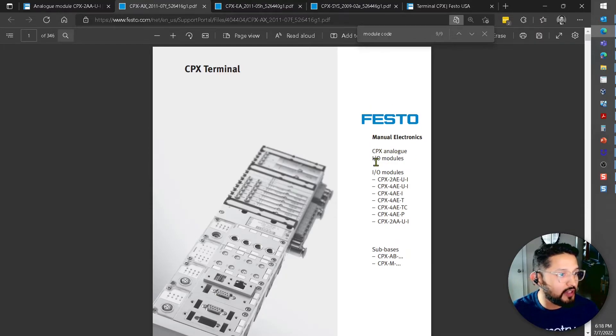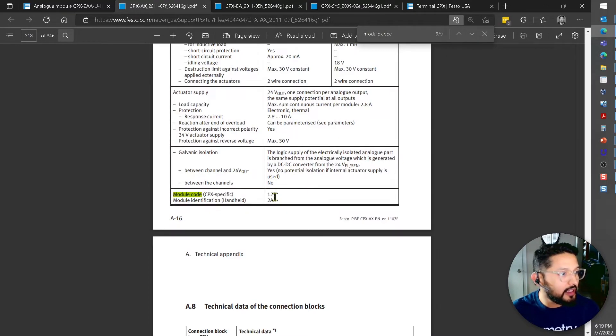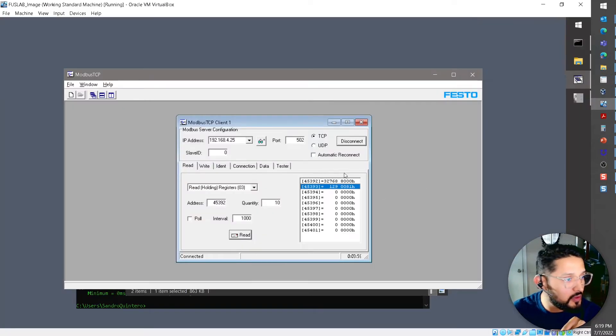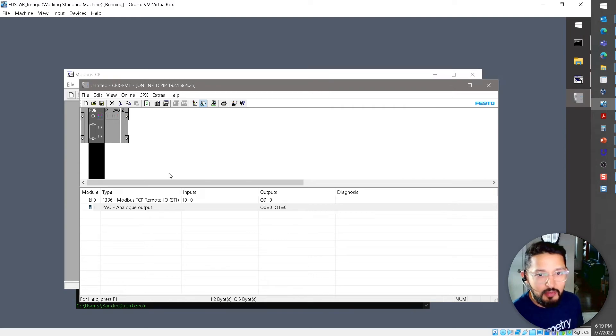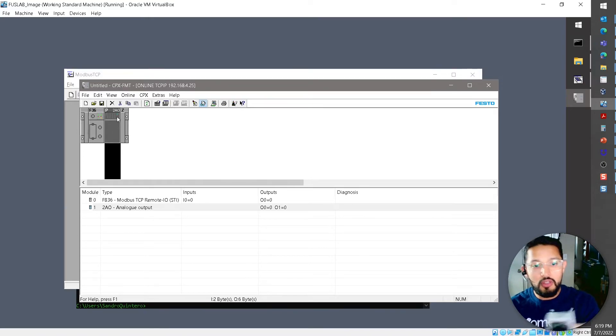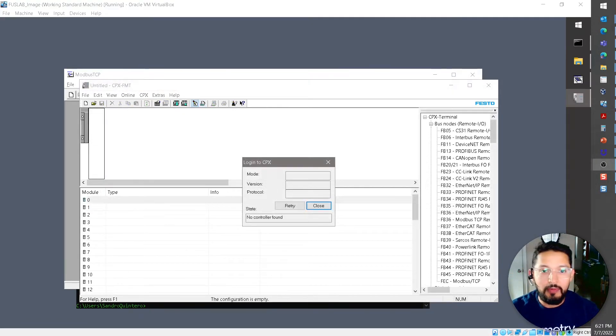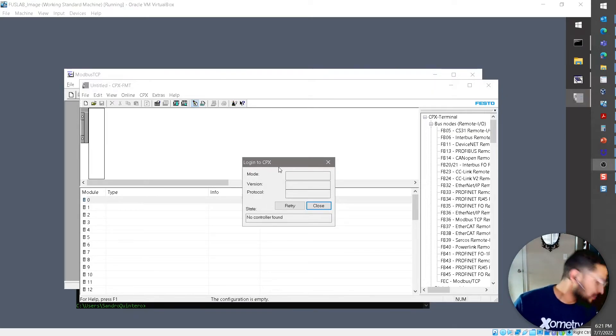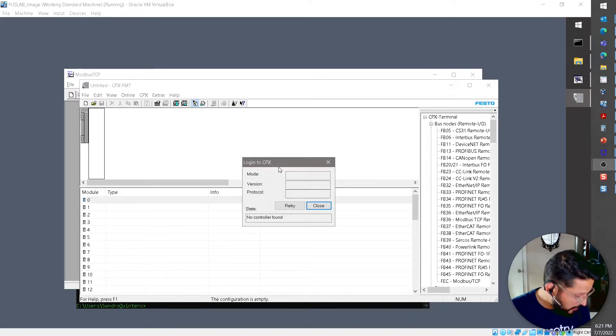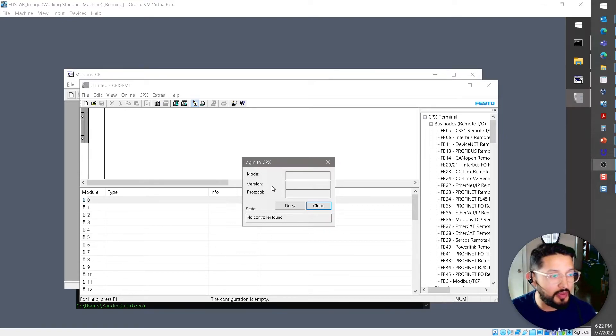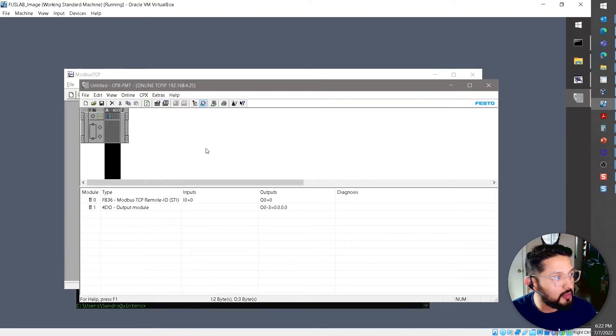If we check the user manual for the CPX analog IO modules, module code 129 corresponds to a two analog output module — which is exactly what's connected. Now I'm going to swap the hardware: I'll power off the CPX, remove the two analog output module, and replace it with the four digital output module.